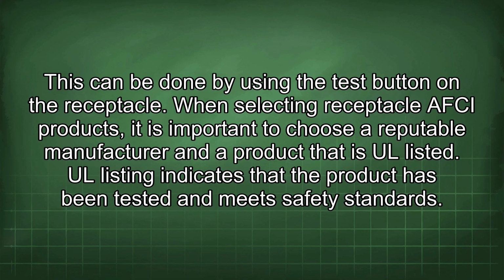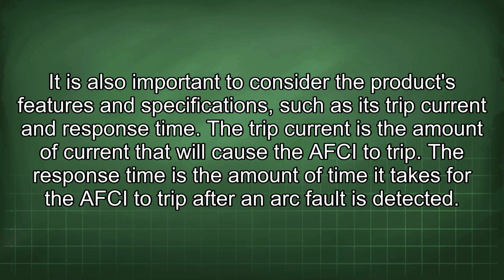When selecting receptacle AFCI products, it is important to choose a reputable manufacturer and a product that is UL listed. UL listing indicates that the product has been tested and meets safety standards. It is also important to consider the product's features and specifications, such as the trip current and response time. The trip current is the amount of current that will cause the AFCI to trip. The response time is the amount of time it takes for the AFCI to trip after an arc fault is detected.